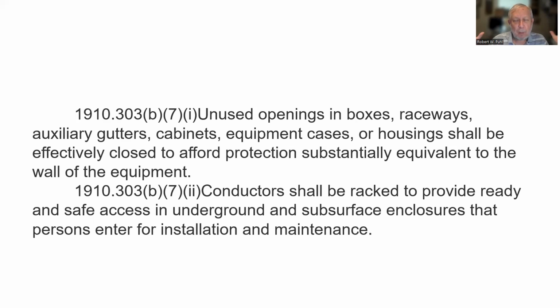Now, anytime you see an electrical panel, they're usually gray boxes, and there are knockout plugs in them to allow stuff to come in and out, conduit and stuff like that. And frequently they get knocked out and don't get covered back up again. That's a violation right here, and you will get written up for that by OSHA. So you've got a box, an electrical cabinet that's got an opening anywhere. Look at the bottom too. That's where it frequently happens. The inspector's going to look at the bottom if he wants to catch something.